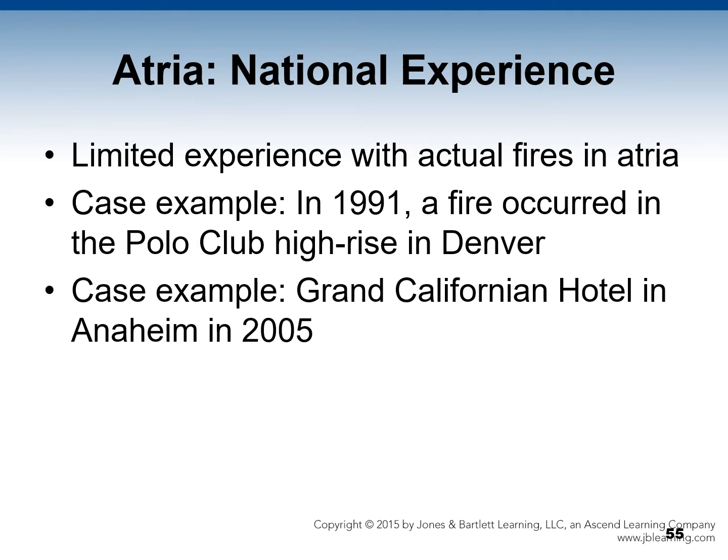Another case example is the Grand Californian Hotel at the Disneyland Resort in Anaheim in 2005. You probably remember seeing this on the news, perhaps. Lights on an artificial Christmas tree ignited, burning off the top third of the tree. Sprinklers contained the fire as 2,000 hotel guests were evacuated. So in this case, it worked like it's supposed to.